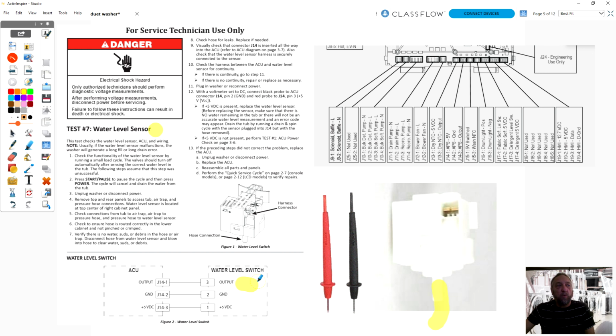The water level switch connects to the ACU, which is the control board. How much voltage does that water level switch run on? 5 VDC. Correct. And where would you put your meter on the board to make that test?